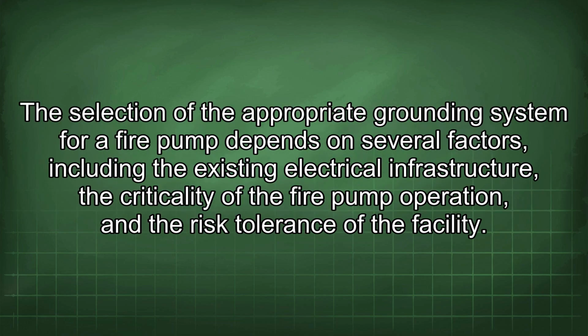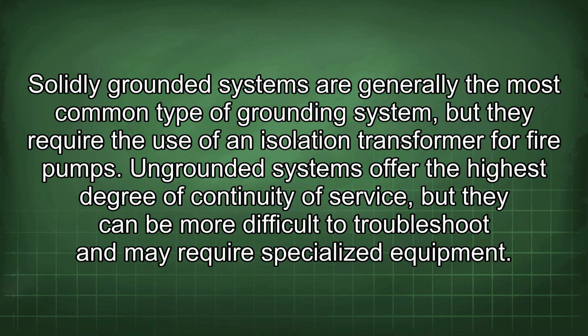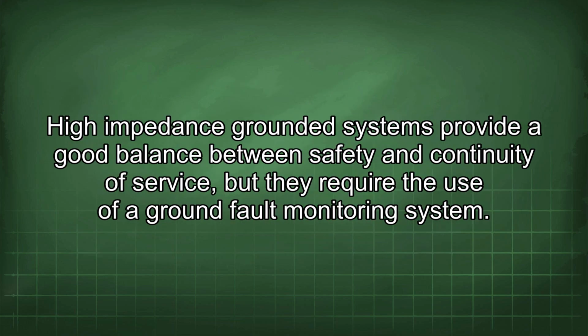The selection of the appropriate grounding system for a fire pump depends on several factors, including the existing electrical infrastructure, the criticality of the fire pump operation, and the risk tolerance of the facility. Solidly grounded systems are generally the most common type of grounding system, but they require the use of an isolation transformer for fire pumps. Ungrounded systems offer the highest degree of continuity of service, but they can be more difficult to troubleshoot and may require specialized equipment. High impedance grounded systems provide a good balance between safety and continuity of service, but they require the use of a ground fault monitoring system.